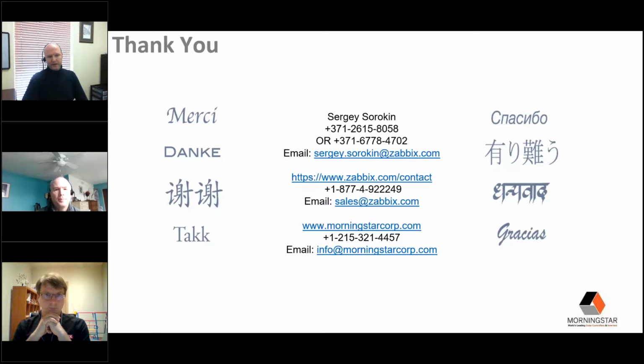Yes, we do track the collective. It really depends on the device. And one of the things you can look at is each controller's template will show you exactly what values we do track. So I want to be careful I don't overstate what the values are, but we have a pretty broad range of everything that's usually available in MS View is also available as a value that can be pulled from the device as well. And we do have both kilowatt hour as well as amp hour input on a lot of the controllers. Again, it's specific to the controller, but that would allow you to measure harvested or collected energy from the PV array, as well as the number of amp hours that are going into the battery.